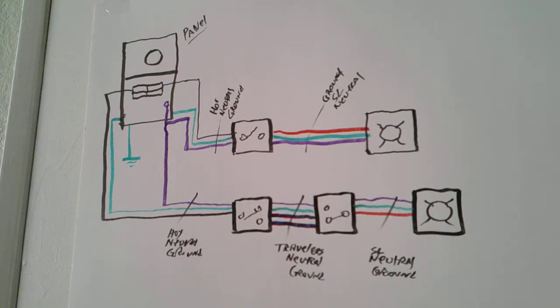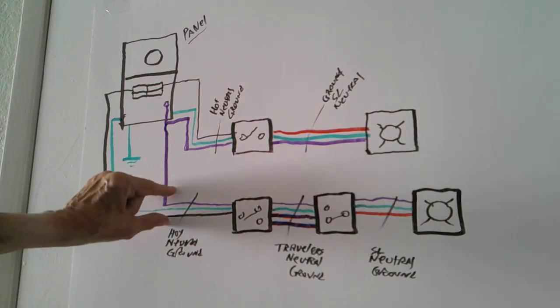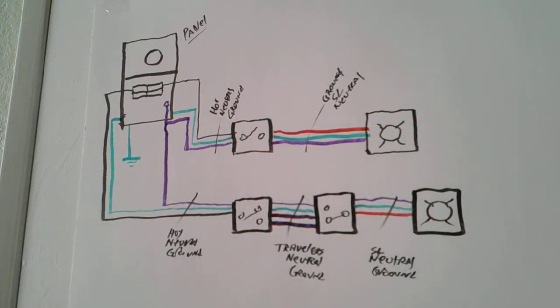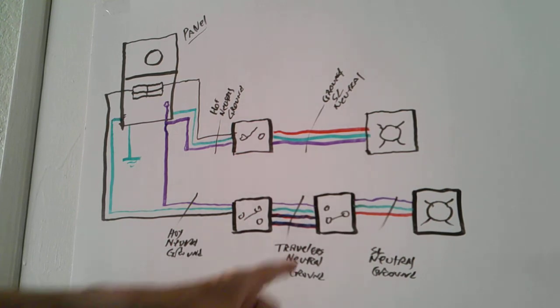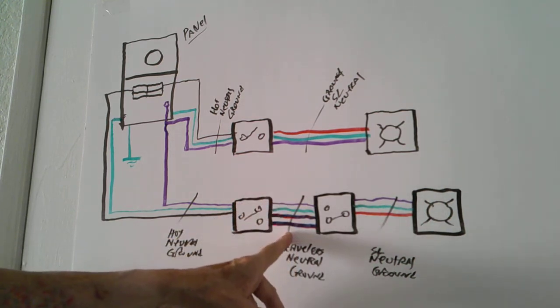And you should check both of those, because if you have no neutral, then you have a problem in this group of wires coming from the panel. Alright, so you have power going to this point here, which is the first three-way switch. You want to check and make sure that this group of wires here is wired correctly.